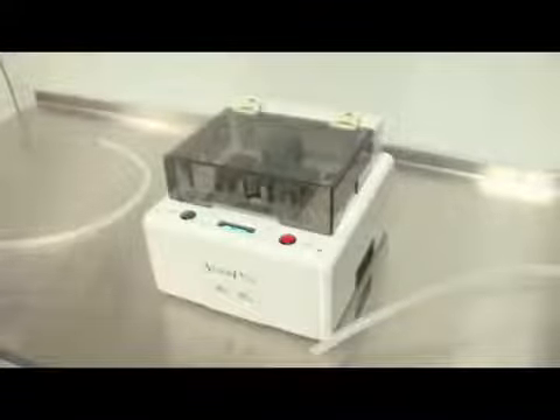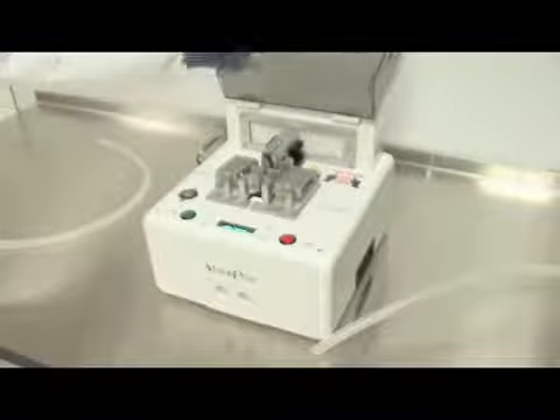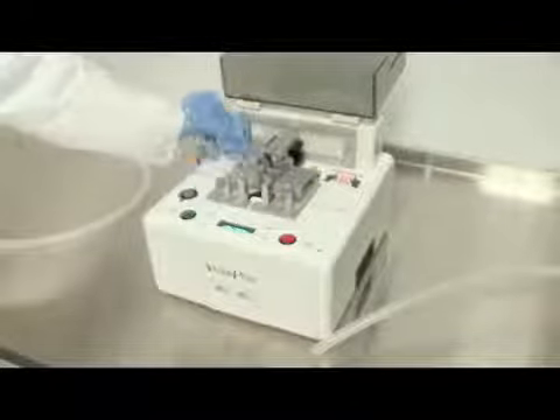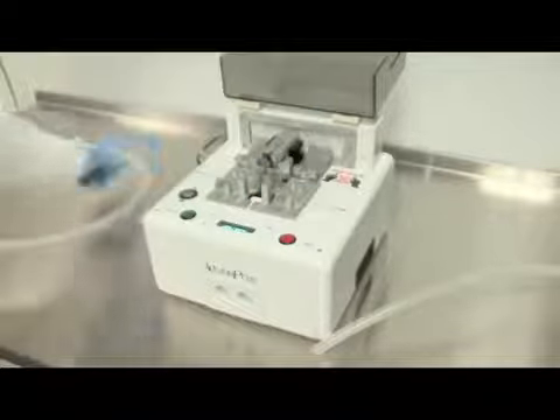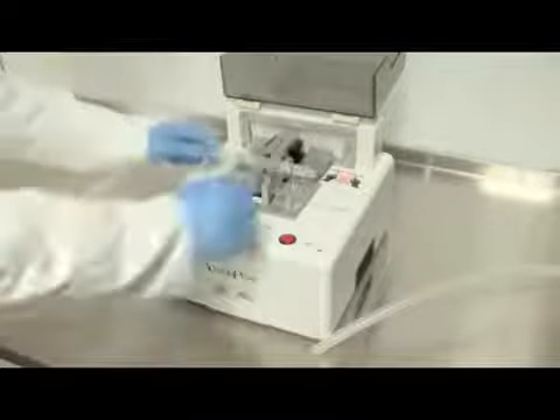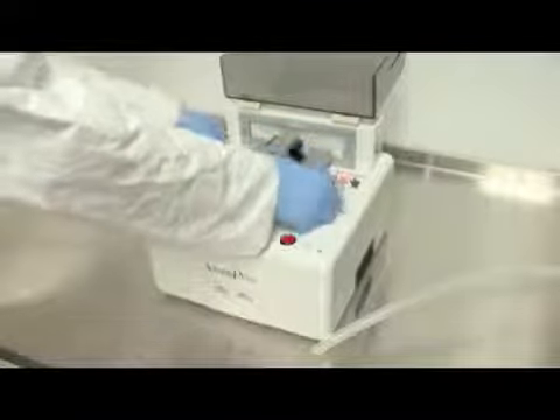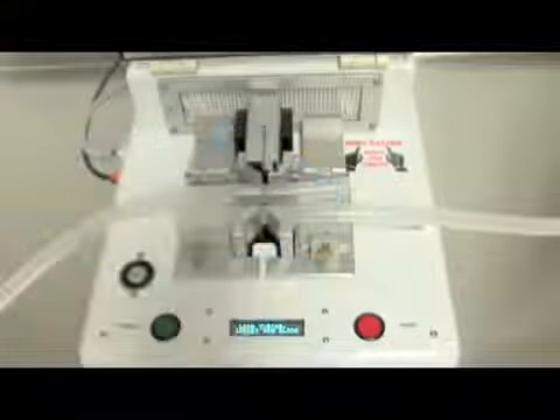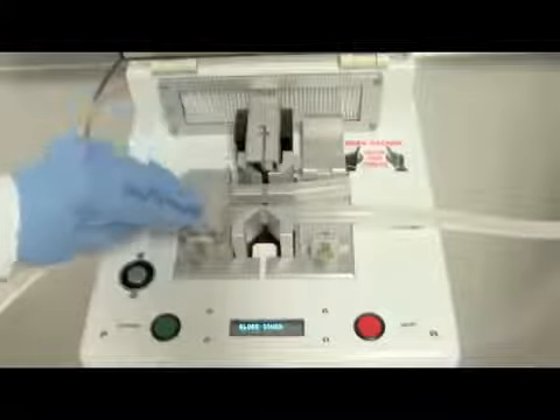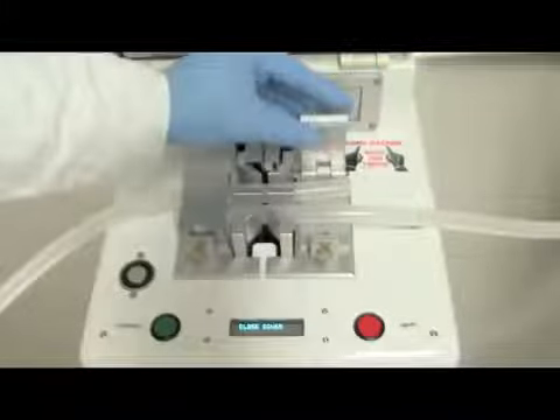Pictured in this video is the AdvantaPure sterile tubing welder. This device allows a validated sterile connection of two lines of tubing, reestablishing fluid flow from a source to a destination. The fluid source tubing line is inserted from the left side of the unit, and the destination tubing line is inserted from the right side of the unit. The clips are then closed to help hold the tubing in place before the cycle is initiated.